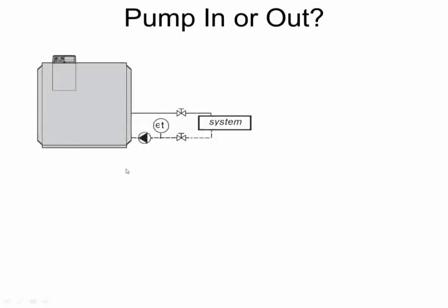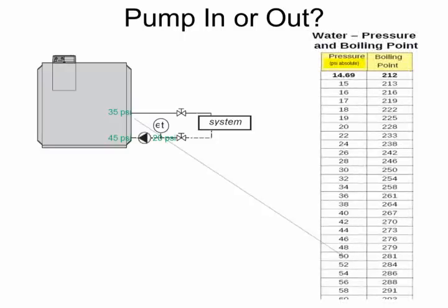Now, this issue of pumping in and out of a condensing boiler, what's going on? Well, as a real simple example, say we have our primary pump, an expansion tank and the rest of our system, and we pressurize the system to 20 psi, and our pump is capable of delivering 25 psi of head, so going into our boiler is 45 psi. Condensing boilers often have a large amount of resistance in them, which means what? Pressure drop. So coming out of that boiler could be 35 psi, and that continues around through our system, losing the rest of the pressure back to 20 psi, starting the process all over again. So the lowest pressure in the boiler heat exchanger is 35 psi.